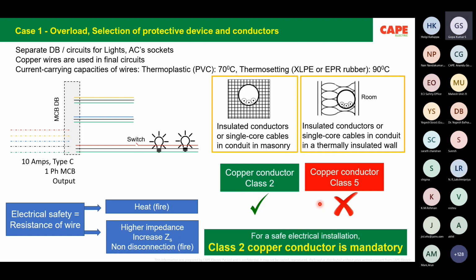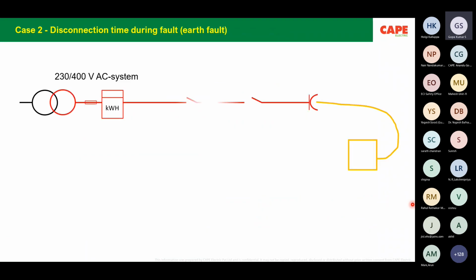We are also trying, once the regulation is out, to take it up with the electrical inspectorates across the country, every electrical inspectorate, and request them to issue a notice, press note or something like that, to make people aware and tell them not to use class 5 copper conductor because of its cheapness or lower cost. All over India, class 5 copper conductors are used. As I said, it's a hazard. Please don't use class 5 copper wires.